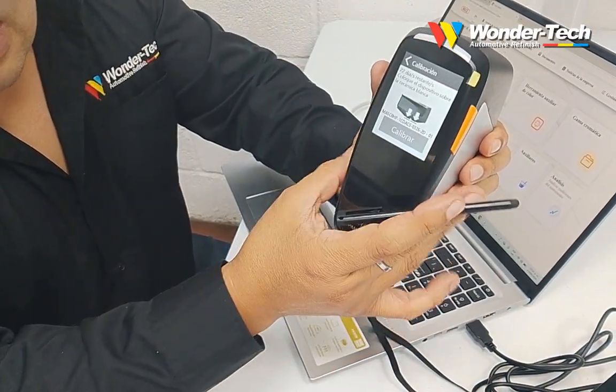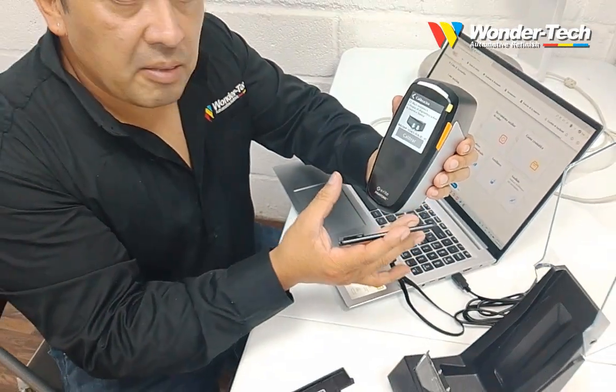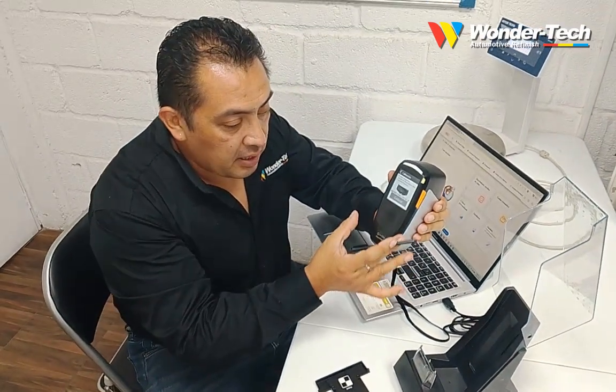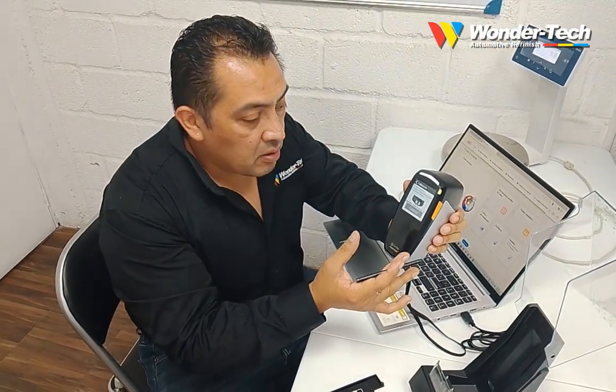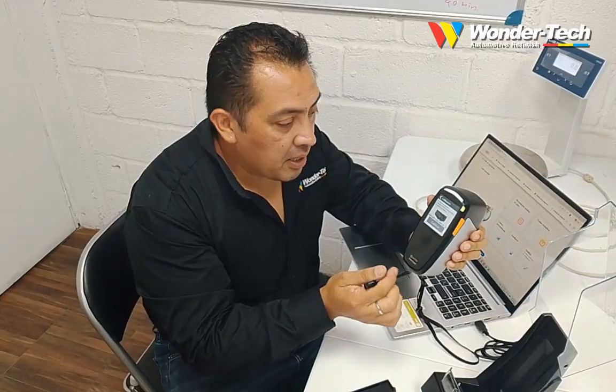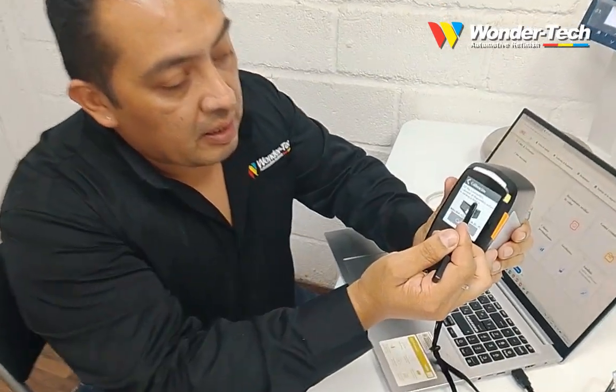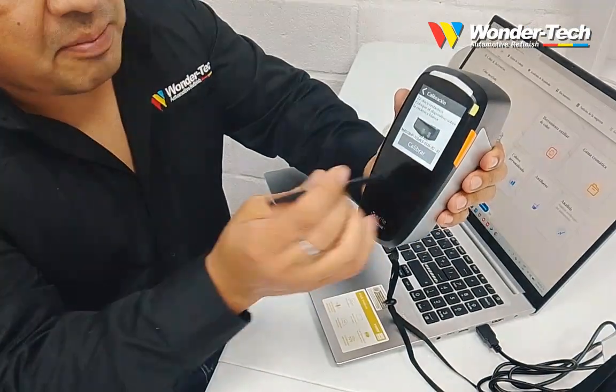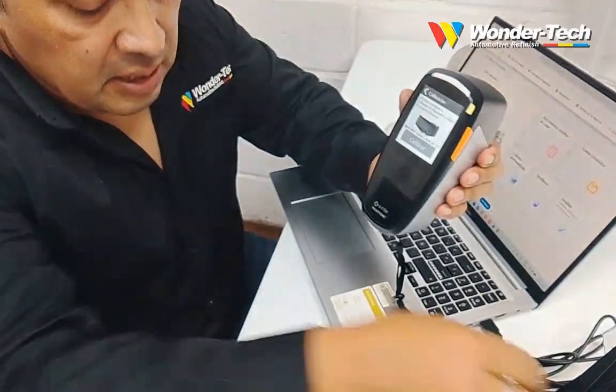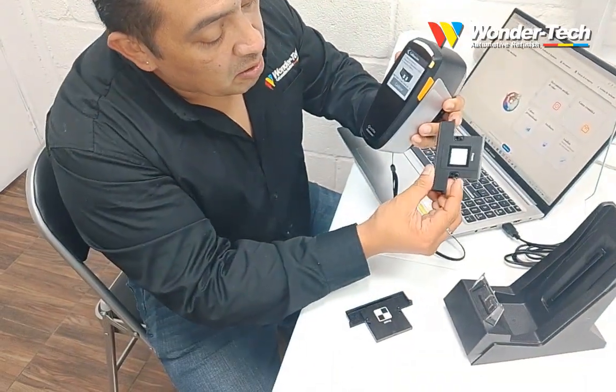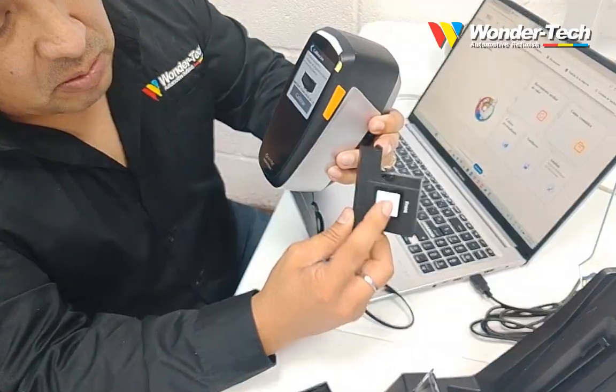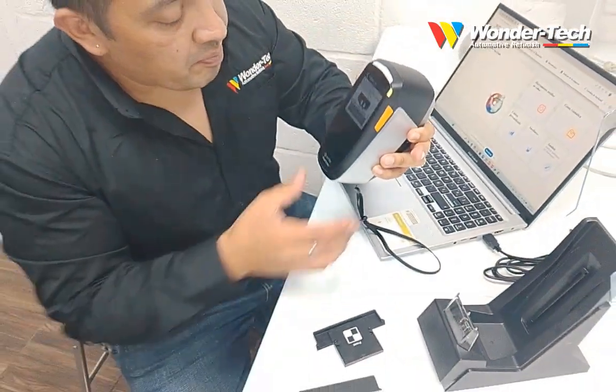As you can see, my device indicates there are 22 days remaining before the next required calibration. Since my instrument is already calibrated, I won't perform the procedure again today. However, I'll show you exactly how the process works. The software first instructs you to measure the white calibration tile.